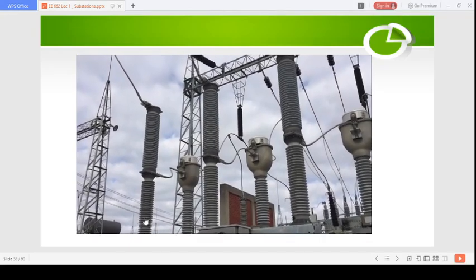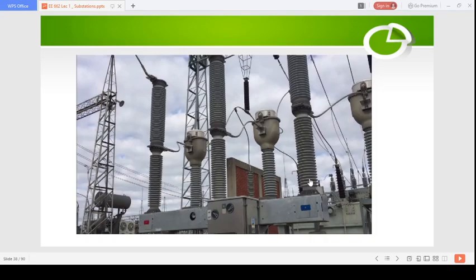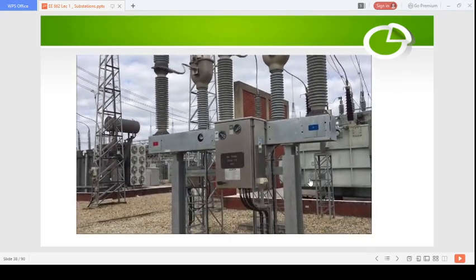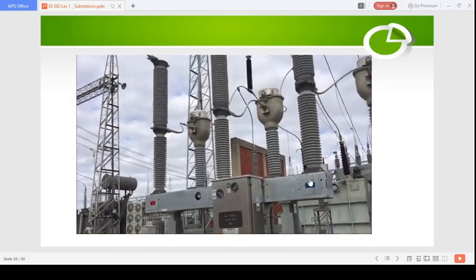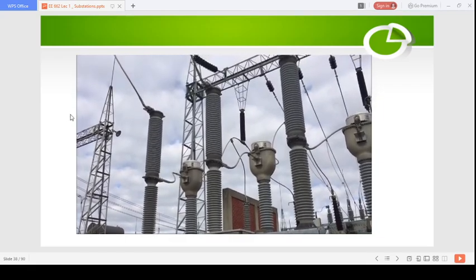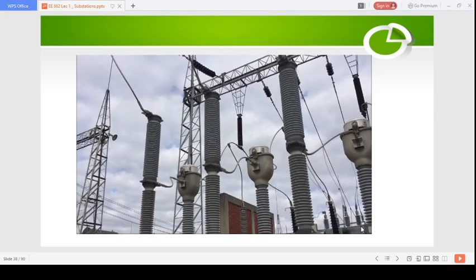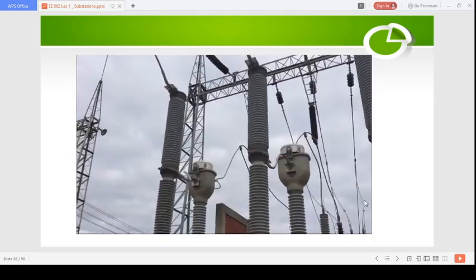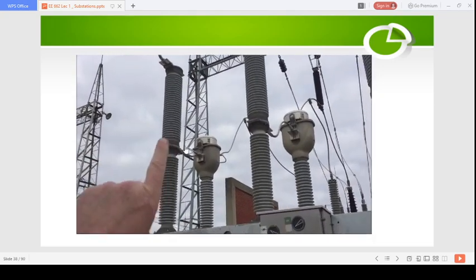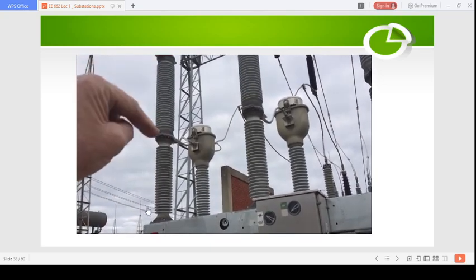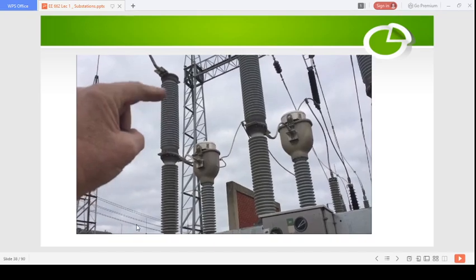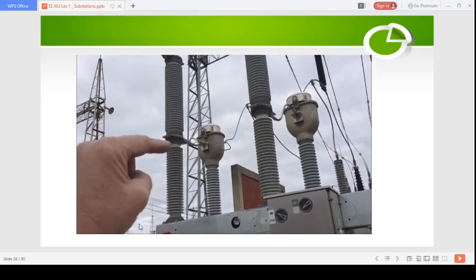This is an Alstom 132,000 volt circuit breaker. It's fairly common these days. The interrupting and insulating medium is sulfur hexafluoride gas, not oil. How it works is, up in the top section there's a copper rod which moves up and down.